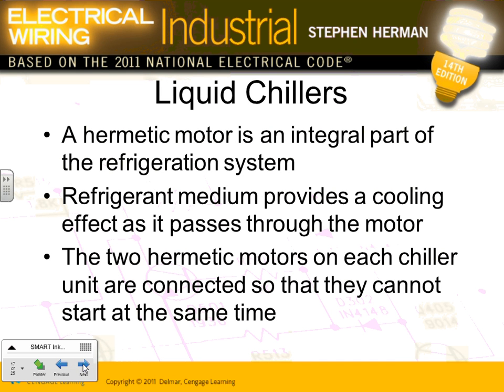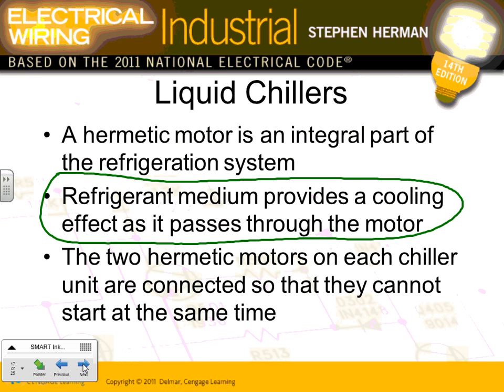Chilled water, we talked about the chiller, guys. I showed you multiple chillers in an example. Part of your refrigeration system provides cooling. This is why they allow you to use a separate coil, and the chillers are special animals, because the refrigerant medium provides cooling effects as it passes through the motor. You can't get this from any other motor. So the refrigerant cools the motor. That's why they call them hermetically sealed motors, guys. Hermetic motors, because they're sealed, are naturally cooled.